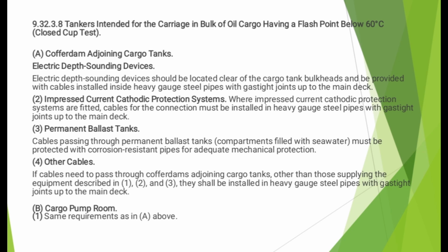Impressed current cathodic protection systems. Where impressed current cathodic protection systems are fitted, cables for the connection must be installed in heavy gauge steel pipes with gas-tight joints up to the main deck. Permanent ballast tank. Cables passing through permanent ballast tank compartments filled with seawater must be protected with corrosion-resistant pipes to give adequate mechanical protection. Other cables. If cables need to pass through cofferdams adjoining cargo tanks other than those supplying the equipment described in 1, 2, and 3, these shall be installed in heavy gauge steel pipes with gas-tight joints to the main deck.